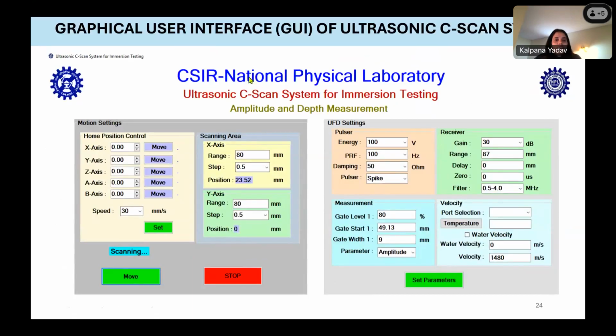So here is a graphical user interface of that ultrasonic C scan system, where you can control your home position control for the motion axis, where you can control X, Y, Z and A, B for the tilt and angular motion. And you can select the scanning area, how much range you want to scan for the samples, and what step you want. And you can control your UFD settings like energy, PRF, that's pulse repetition frequency, damping and pulser, and the receiver frequency. And you can set your gate, whatever you want to measure inside that gate, and the velocity section for the water velocity and the velocity of the material.